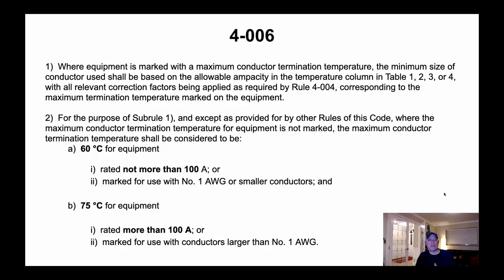Sub-rule 2 states: where the maximum conductor termination temperature for equipment is not marked, the maximum termination temperature shall be considered to be 60°C for equipment rated at not more than 100 amps or marked for use with No. 1 AWG or smaller conductors, and 75°C for equipment rated more than 100 amps or marked for use with conductors larger than No. 1. So up to and including 100 amps, treat it as 60°C; exceeding 100 amps, treat it as 75°C.